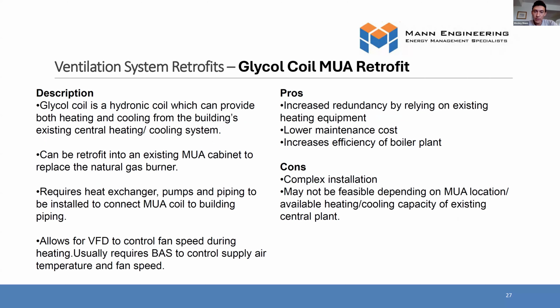Okay, so glycol coils. This is something we can really help out with. We do a lot of these projects because it's actually a great long-term solution for the makeup air. What you're doing is eliminating the gas-fired burner, which is another gas appliance you have to maintain, and typically they have pretty low efficiency. And you can actually heat the makeup air directly from your existing boiler plant. So this works well if you have a penthouse mechanical room. We can pipe in a heat exchanger to provide a glycol loop. It has to be glycol because, again, it's outdoors, and with makeup air systems, the air is very cold.